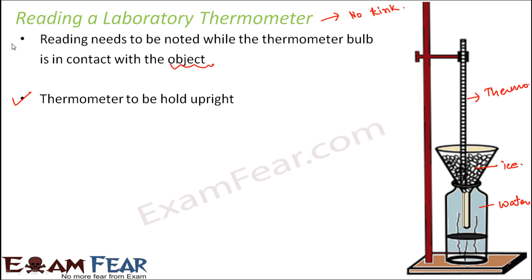Secondly, the thermometer must be held upright — this is another difference from the clinical thermometer. With the clinical thermometer, slight tilting doesn't matter as long as the bulb is under your tongue. But with the laboratory thermometer, tilting changes the heat available to the bulb and therefore changes the reading. It is very important to hold it exactly upright. That is why in most laboratories the thermometer is provided with a clamp stand — fix the thermometer in the stand, insert it into the solution, and immediately note the temperature.